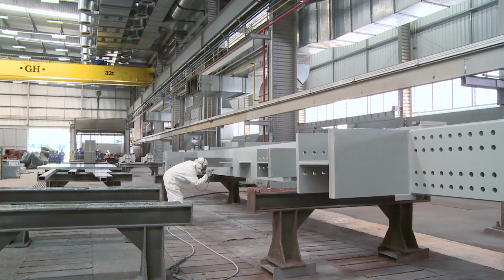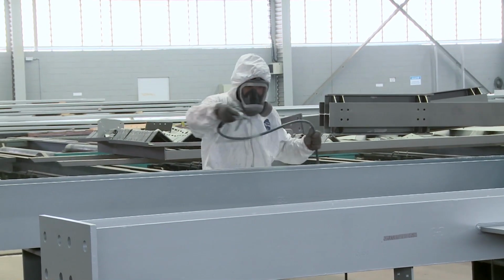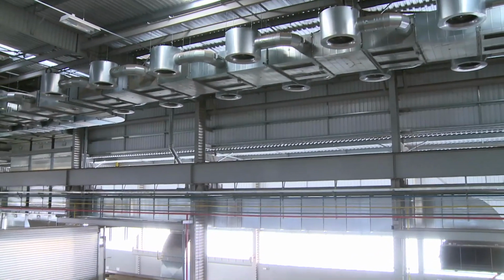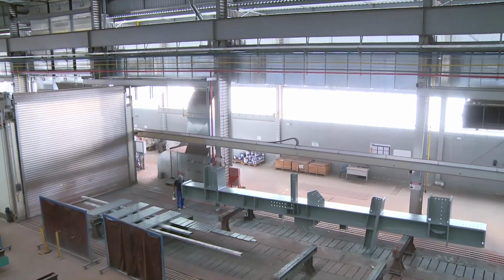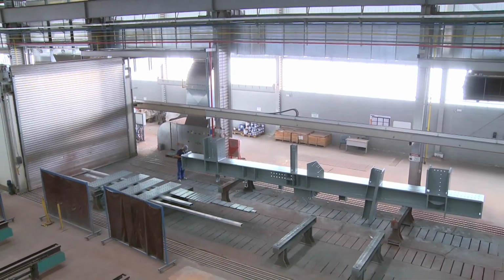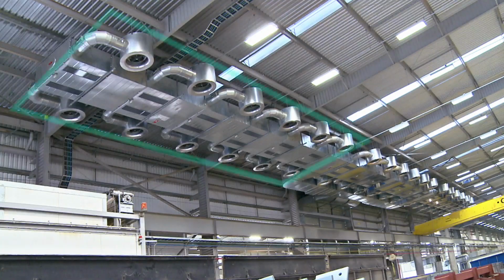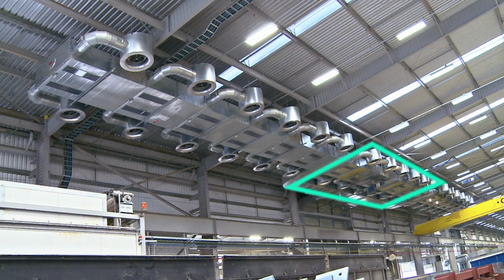2 technicians can work at the same time in the active spraying zone. As an example, with an incoming and exhaust air capacity of 50,000 cubic meters an hour, our system can handle the airflow for a floor space covering approximately 50 square meters. Using a series connection, a single ventilation system can supply shifting work areas with heated air and extract the exhaust air with a high level of energy savings. The coating technician more or less takes his supply of fresh air with him wherever he goes.